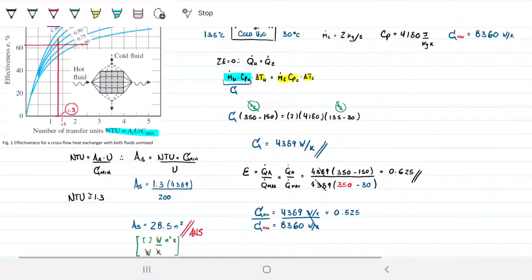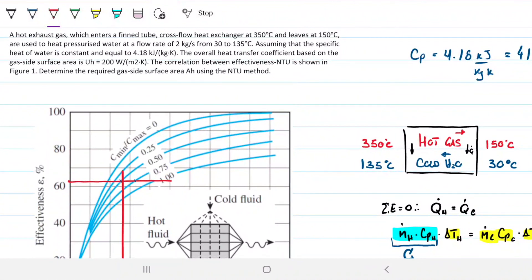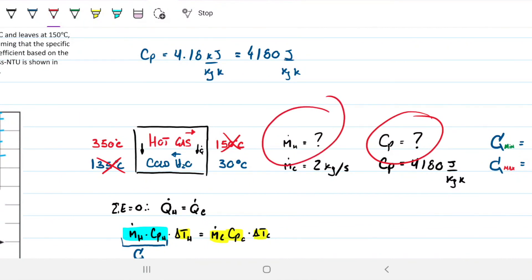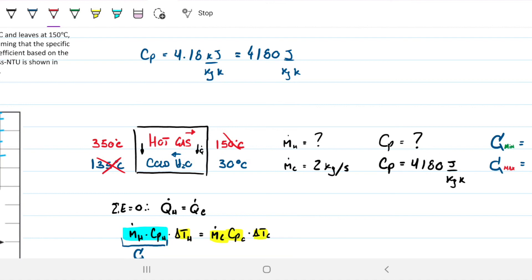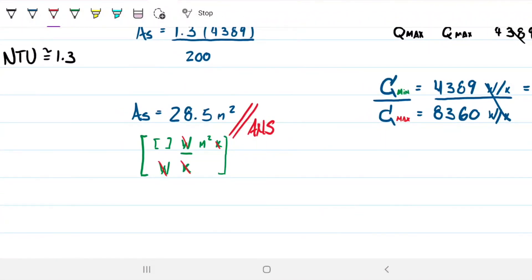Hopefully you can appreciate that this method is quite powerful. Even though we didn't have all the fluid-side information, we could still calculate the required surface area on the gas side. As long as you know the inlet and outlet temperatures, specific heat, and mass flow rate — which you generally do when designing a heat exchanger — you can solve this using the NTU method. If you have any questions, just let me know; otherwise we'll talk soon.